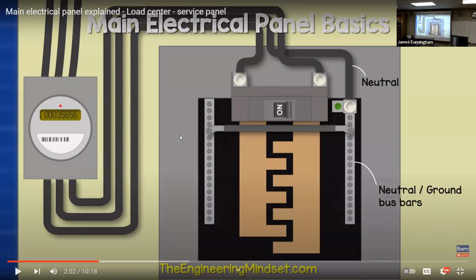So in your main panel, this is my ground bus bar on this side, and this is my neutral bus bar on this side. And this is where the white wires go, right? So the neutral bus bar is where my white wires go. The ground bus bar is where my green or my bare wires go.